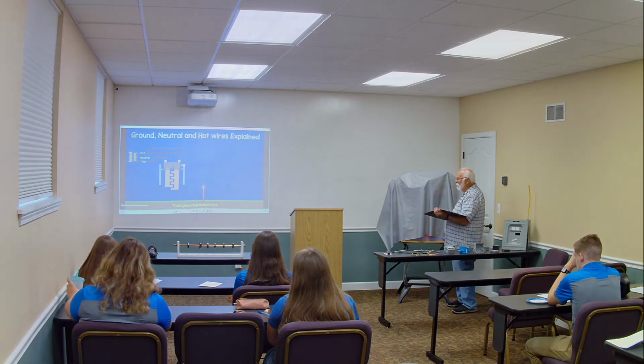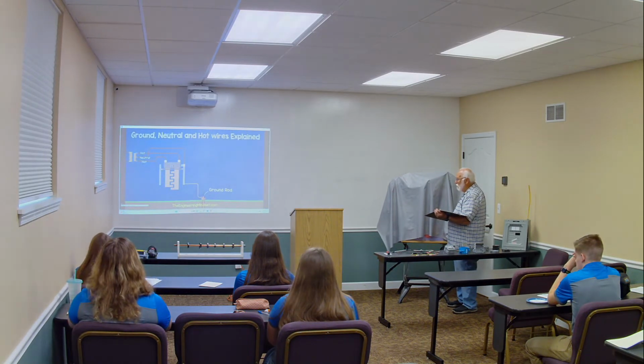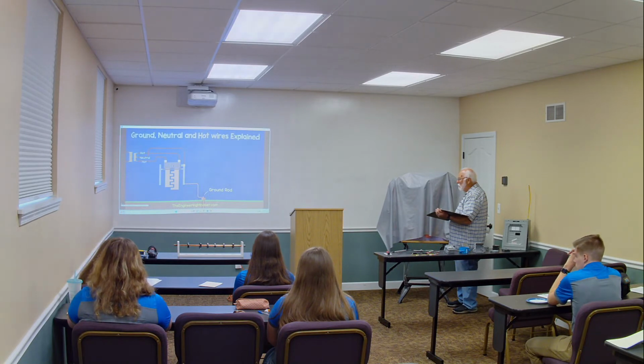Connected to the main panel, we find a thick copper wire which leads out to a ground rod. The ground rod is buried into the ground outside near the property. This rod is not used for ground faults. Its purpose is to dissipate static electricity and external high voltages like lightning strikes. There is also a ground rod connected to the neutral at the transformer.